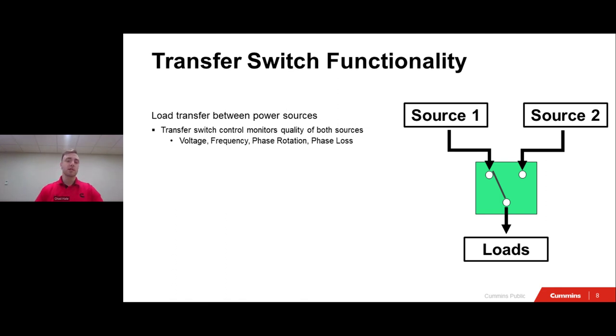Now that we have established the what and the why, let's step into some high-level functions of a transfer switch and how they work a little bit more in depth. So, for starters, we have that load transfer between sources. This is what you will most commonly see with automatic transfer switches. You will have a switch that is monitoring the quality of two sources, those two sources most likely being a normal source of the utility, and then you have the ATS monitoring the emergency source that is your backup generator.